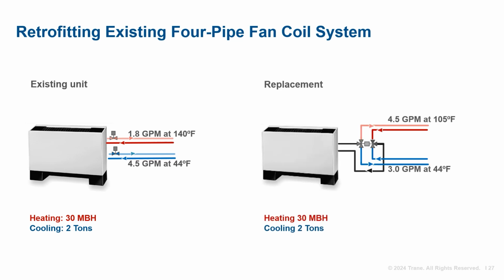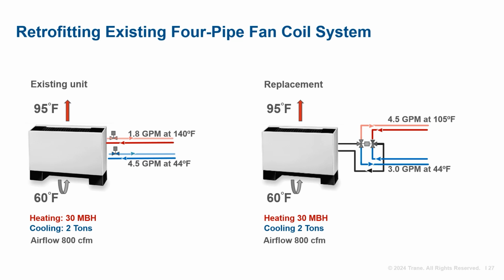The replacement fan coil has a single 4-row dual-purpose coil. It is designed for the same heating capacity using 105-degree glycol with a 15-degree delta T. For cooling, it uses the same 4-row coil to achieve the same cooling capacity. It needs 1/3 less flow and has an 18-degree delta T. Extra airflow is not needed to meet heating capacity. The previous 95-degree design heating leaving air temperature is achieved with 105-degree hot water.